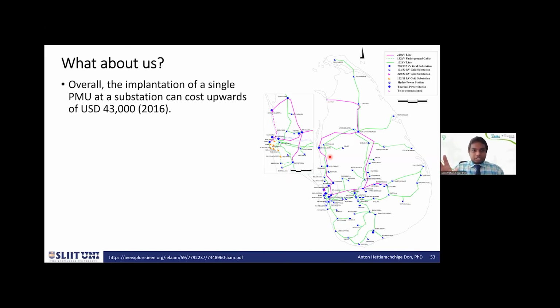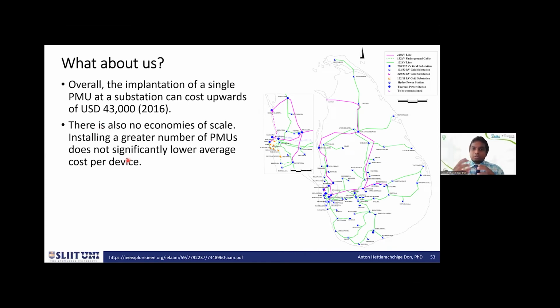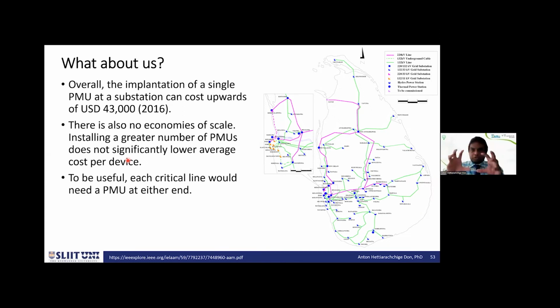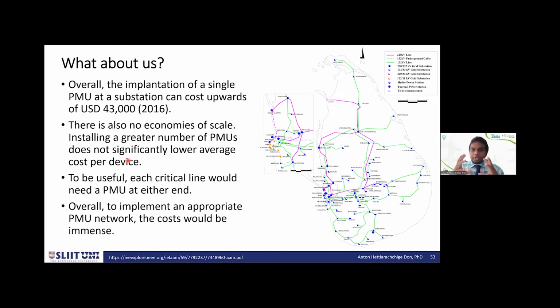So in 2016, an installation of a single PMU cost about 43,000, and of course you can guess right now it would be much higher, right? And also there is no economy of scale: when you want to install 1,000, it doesn't make the per PMU cost any lower because of the way it is. And to make good use of your network, you actually need a lot of PMUs. You cannot have good observability with a single PMU. Each critical line would need 2 PMUs at either end, and they would have to be all connected together for multiple lines to get good observability. So the cost would be immense to do this.